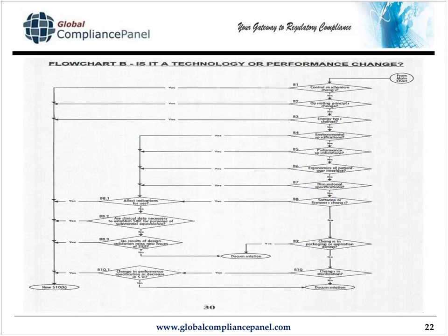Okay. If you look at B10, the question is, change to sterilization, yes or no? In this case, the questioner says, yes, we are absolutely changing from steam to gamma. So the question then is, is there a change in performance specifications? What that means is, when your device, the performance of your device under steam, the previous sterilization, how does that performance compare to the performance of your device after exposure to gamma sterilization? Not just performance, but also physical characteristics.